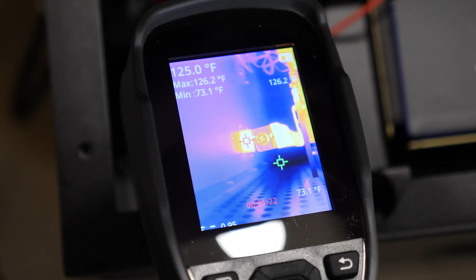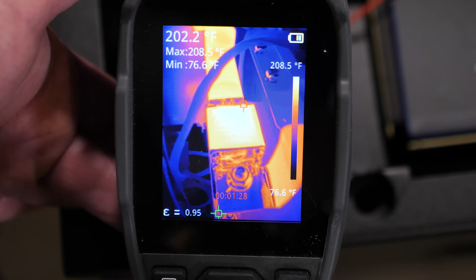That's pretty warm. The other side of the bus bar is showing around 120 degrees Fahrenheit. That little hot spot over there is 124 degrees. So the bus bars where they go in and out of the battery aren't too bad, it's mainly just the fuse right here at 206 to 207 degrees Fahrenheit. Seems to be holding there right now, so we'll just let it go.